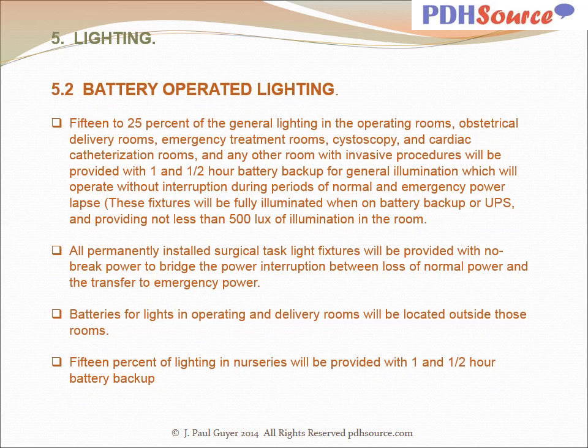Fifteen to 25% of the general lighting in the operating rooms, obstetrical delivery rooms, emergency treatment rooms, cystoscopy and cardiac catheterization rooms, and any other room with invasive procedures will be provided with 1.5 hour battery backup for general illumination, which will operate without interruption during periods of normal and emergency power lapse.